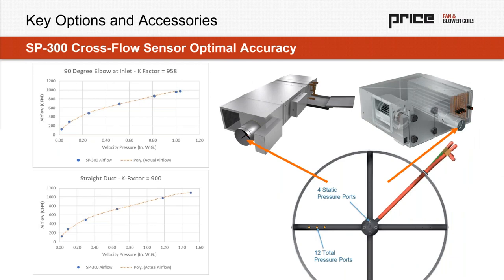So this is testing that we actually did recently for a project. And you can see with this testing, we have the actual airflow that would be measured on this kind of yellow dotted line. And then we have, at a number of different points, airflow measured after testing and balancing with the crossflow sensor. And in this case, it's actually plus or minus 1% with an elbow directly in front of the unit with a 90 degree elbow at the inlet. The same product, the same crossflow sensor, but a straight duct connection, we can see once again plus or minus 1%. So really almost no influence in this case from duct install whatsoever.